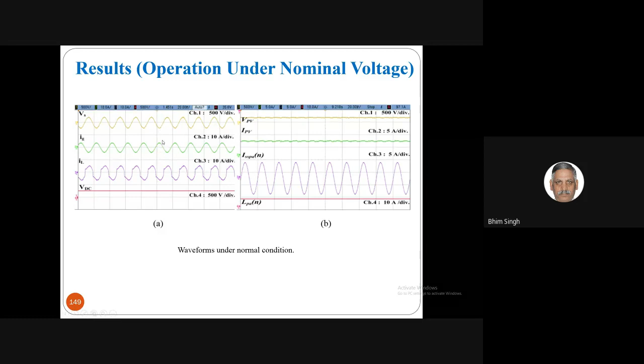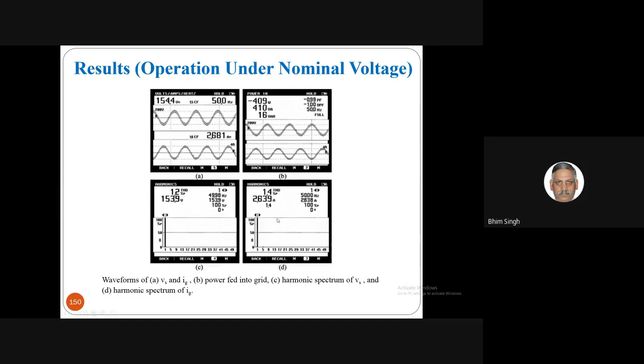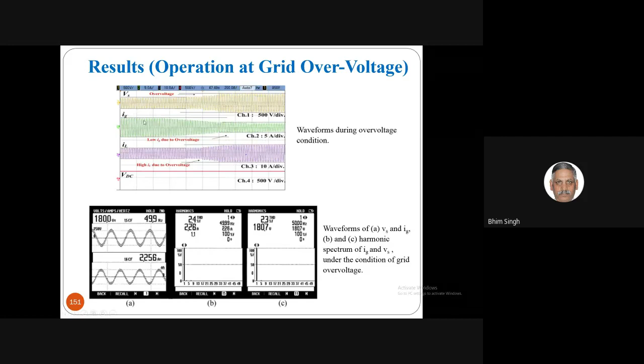We are able to reduce the THD of the grid current to only 1.4%. Our standard typically allows around 5%. Even with 1.2% voltage THD, current THD is only 1.4%. In some cases, like here, the voltage THD is 2.3% but current THD is 2.4%. And with solar power generation, you can see the voltage is changing. Even if you have over voltage, the system works without any problem. Even if there is under voltage, the system works perfectly all right.